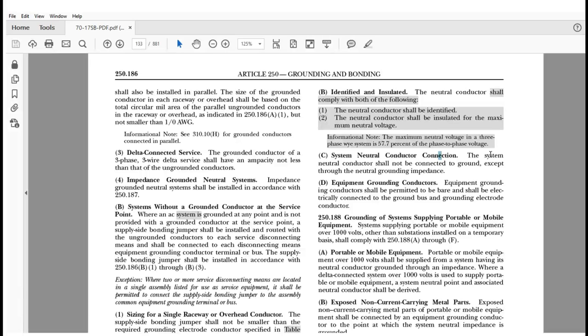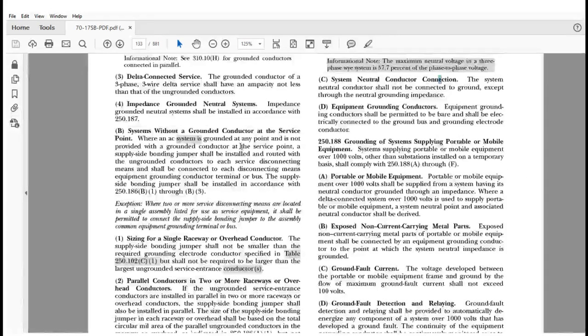That application. It's also important to understand that this is very true for a three-phase Y system only, okay? So you really have to coordinate with the engineering firm that is doing this calculation to really meet this and understand that the neutral conductor shall be identified, which is pretty easy. We understand how to identify the neutral conductor in this case. But we also have to make sure that it is insulated for the maximum neutral voltage here. Okay? And again, the informational note adds clarity to what we're talking about when it comes to the magnitude of neutral voltage here. All right, so I believe that's it for those.